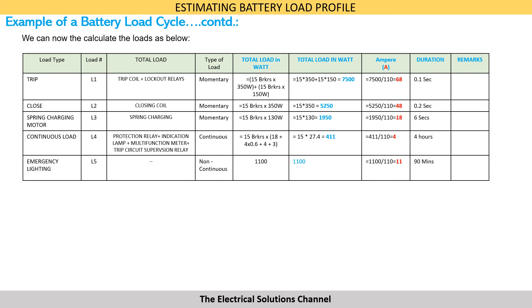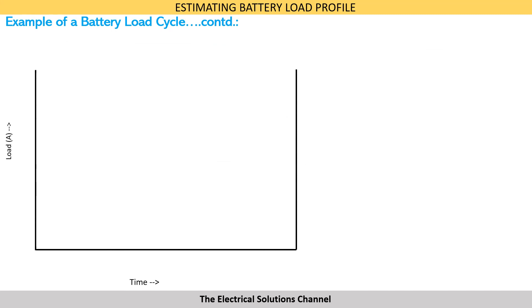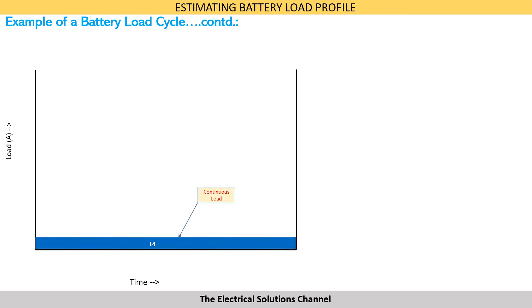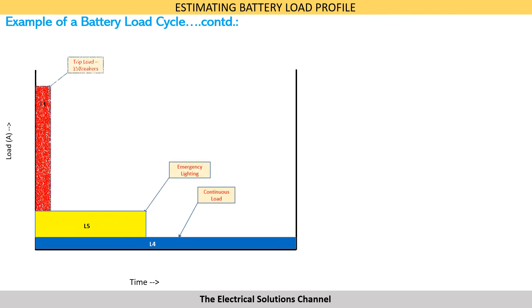The duration of the continuous load in our example will be approximately 4 hours. The load for emergency lighting works out as 11 amps, with a duration of 90 minutes. Once the individual loads have been calculated, we can compile these loads in a graphical form as per the sequence of operation discussed earlier.